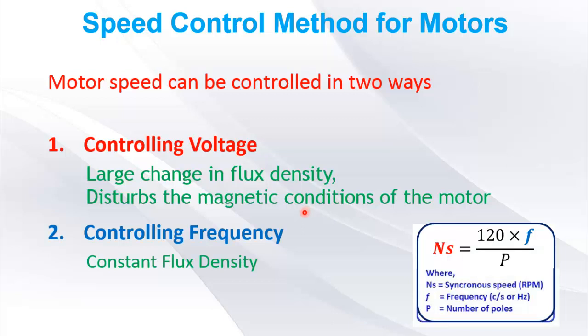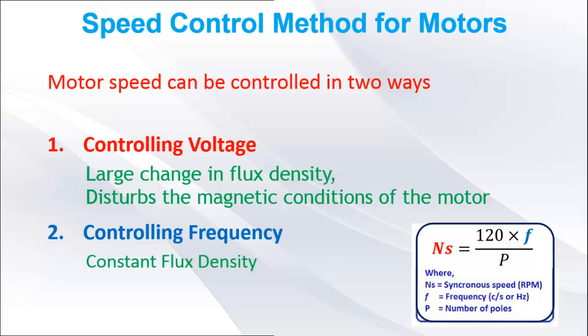The most efficient method of changing speed is by controlling supply frequency, as supply frequency is directly proportional to motor speed in RPM. The flux density also remains constant. But wait, only changing the frequency of motor to control its speed will not apply on all loads.